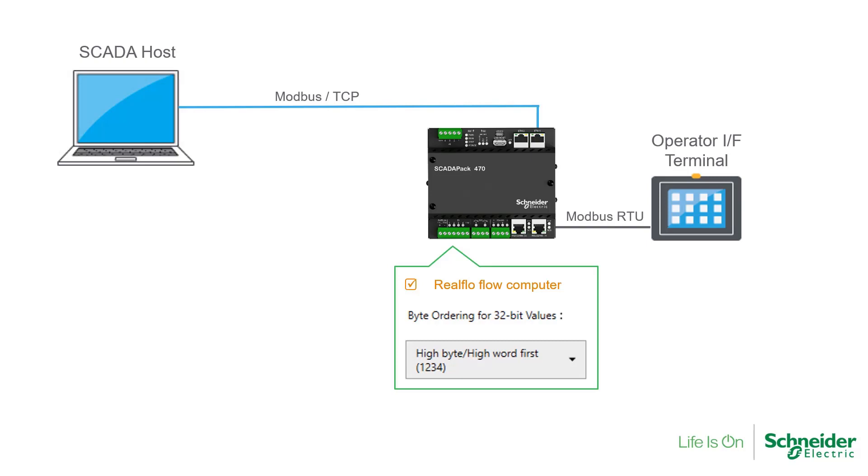This includes a Modbus operator interface terminal or a Modbus SCADA host connected to the SCADA pack. Note also that this setting change applies to Modbus server mode only.